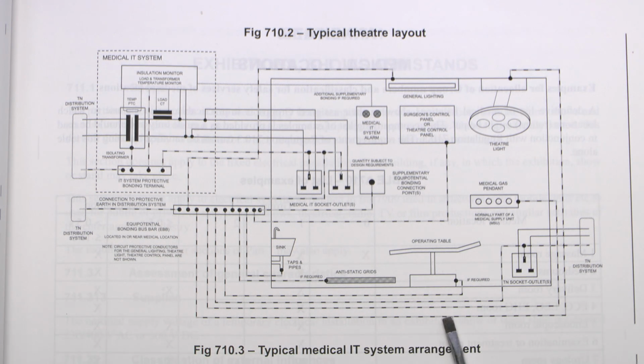One of the more useful changes is that we've actually got the addition of having some TN socket outlets here from a separate distribution system, and how those could be incorporated into the whole. And there's also quite a lot of extra equipment being added in here as examples of what could or may well be found in these types of installation. And so you need to get the old microscope out to actually read some of this text.